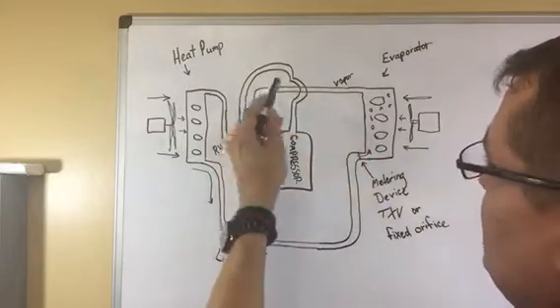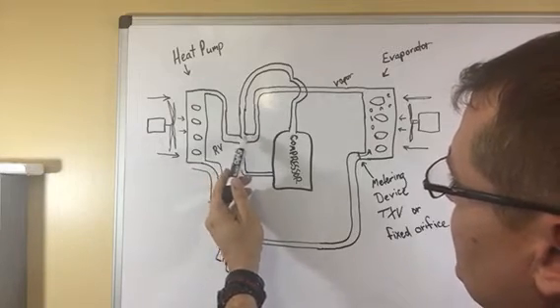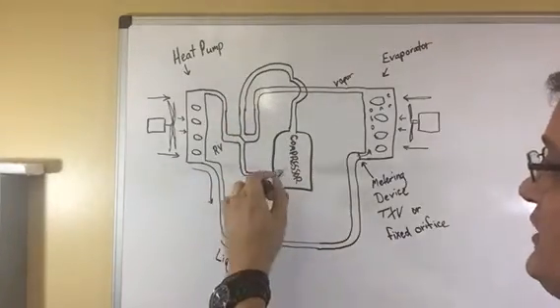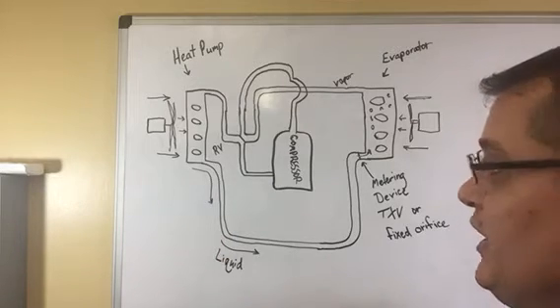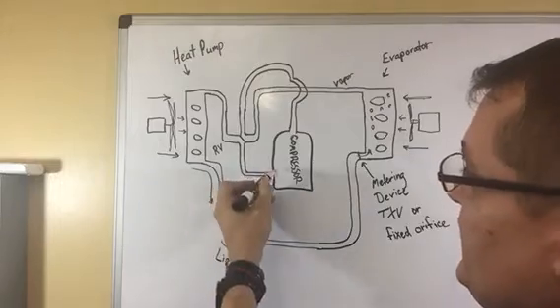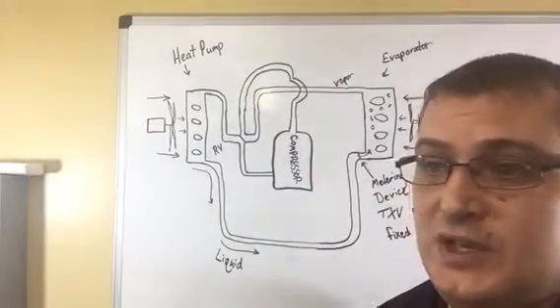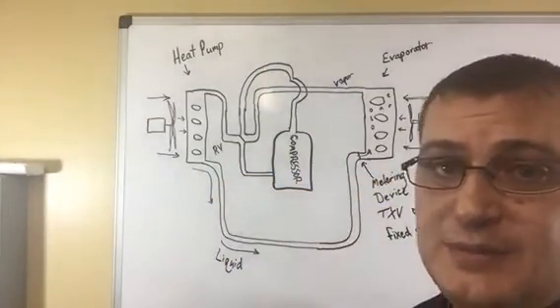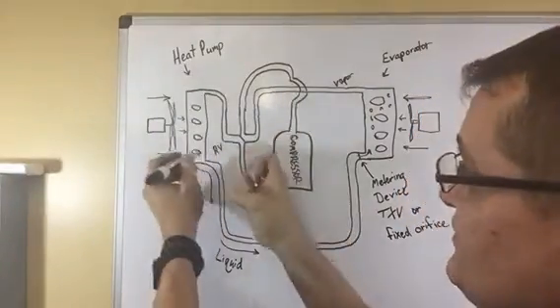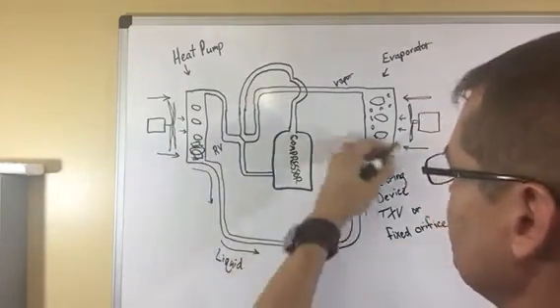That vapor comes through here, through the reversing valve. That's what this is. Comes back to the compressor as a vapor. The compressor compresses that vapor to a hot gas. It just adds heat to it because we're adding pressure. So we add pressure to it, which adds heat to it. Comes out of the compressor, goes to the outdoor coil. And with that fan blowing air across that coil, you're condensing that hot gas back to a liquid. So it condenses back to a liquid, fills up down here, then you got liquid. So it starts all over again.